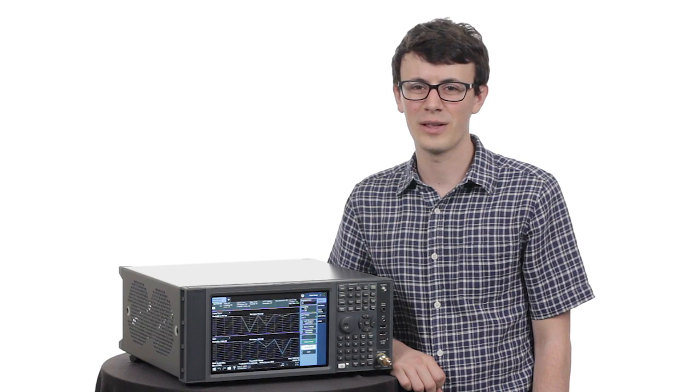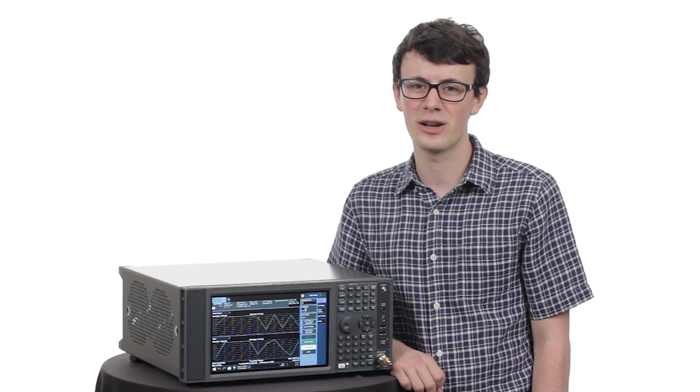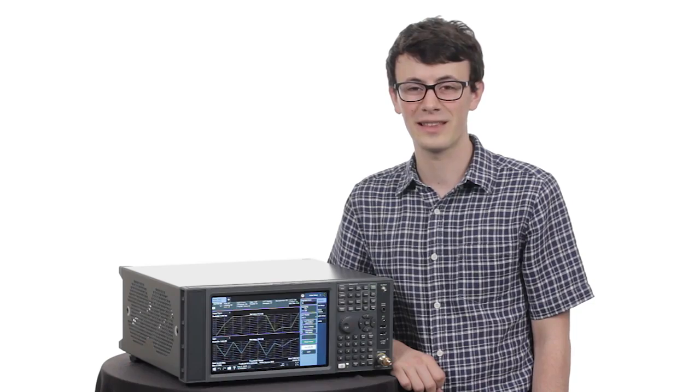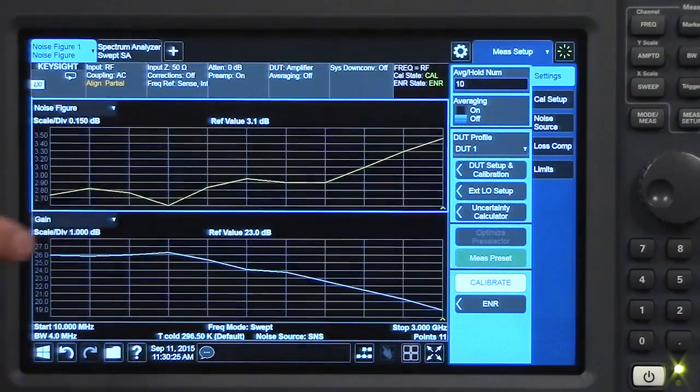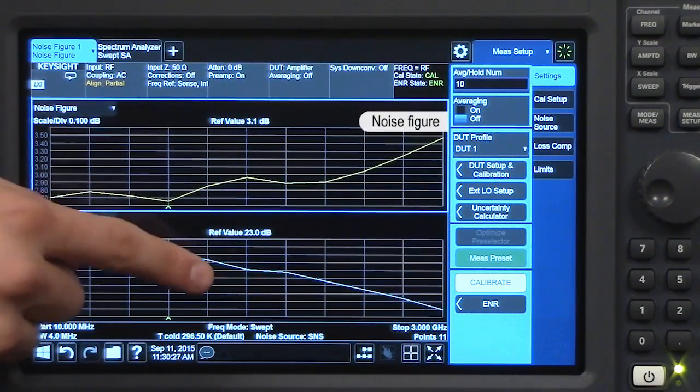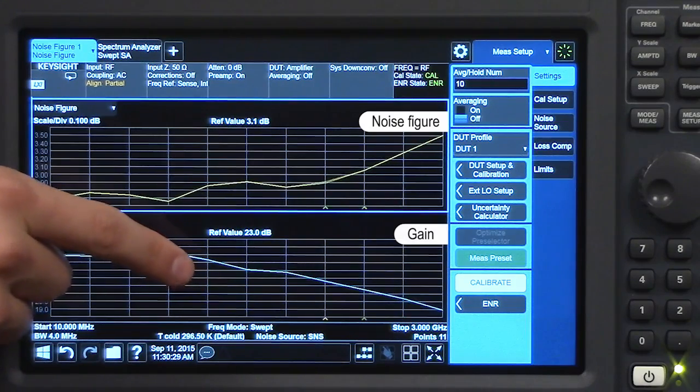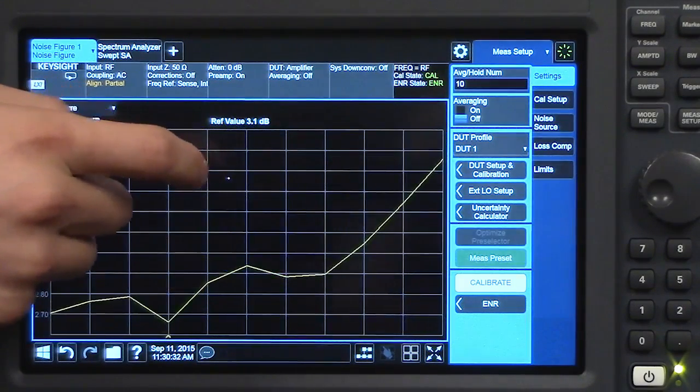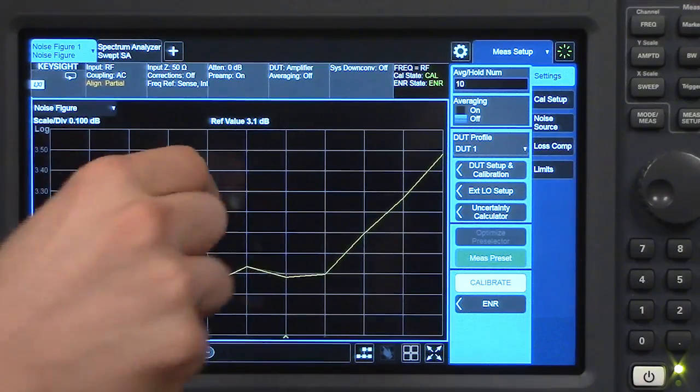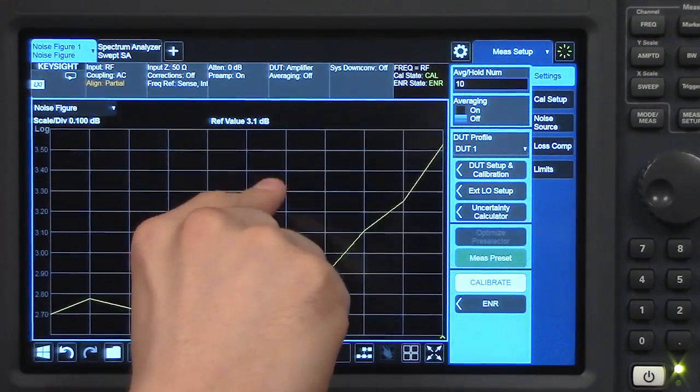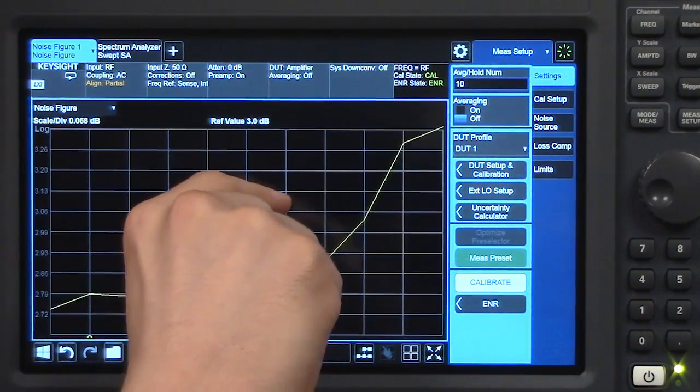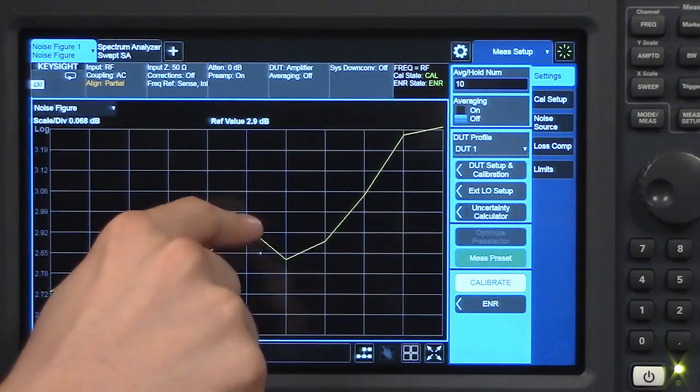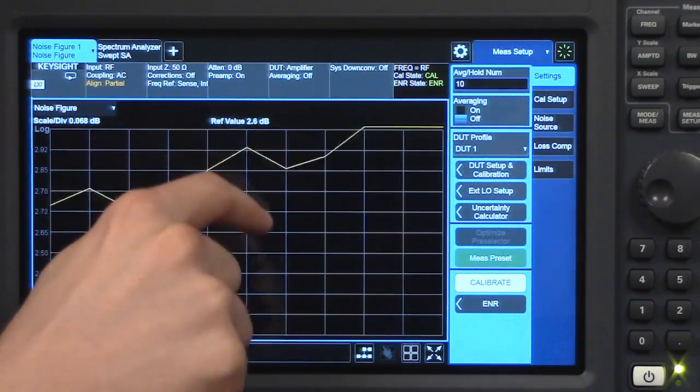Today, I want to demonstrate the multi-touch user interface of our X-Series NFA. Let's get started. We are looking at the noise figure and gain trace of an amplifier. If I double tap this noise figure trace, you'll see that it zooms in. I can then use two fingers and a pinching or zooming gesture to scale that trace. With one finger, I can adjust the reference level.